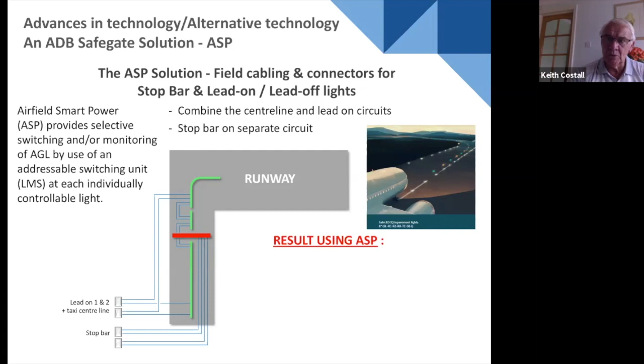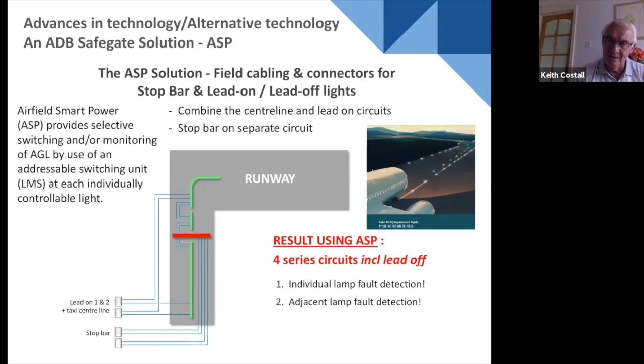Here we start to look at the number of circuits applicable in this technology. The result is only 4 circuits, including the lead-offs, with individual light control and monitoring, and adjacent lamp fault detection capability. That's a major saving in infrastructure.